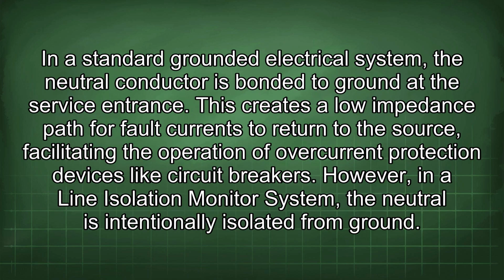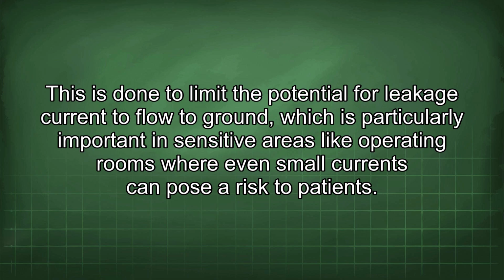In a standard grounded electrical system, the neutral conductor is bonded to ground at the service entrance. This creates a low impedance path for fault currents to return to the source, facilitating the operation of overcurrent protection devices like circuit breakers. However, in a line isolation monitor system, the neutral is intentionally isolated from ground. This is done to limit the potential for leakage current to flow to ground, which is particularly important in sensitive areas like operating rooms where even small currents can pose a risk to patients.